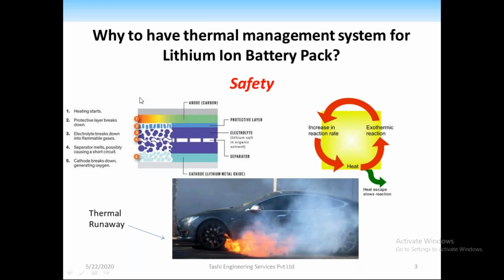That's the stage when we say it's in thermal runaway, and our prime motive is to avoid this. Thermal runaway doesn't happen at a particular temperature like 120 or 130 degrees Celsius - it's much more of a process. It starts from 70, 80 degrees Celsius, and it can be avoided if we have a proper battery management system and thermal management system.